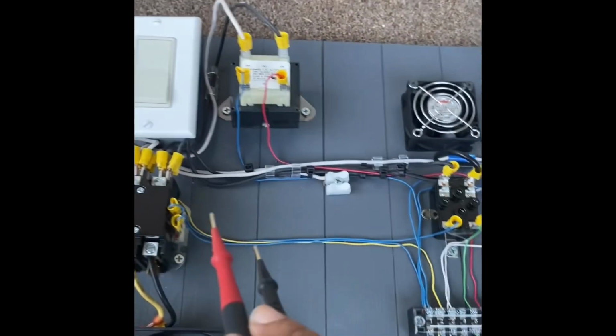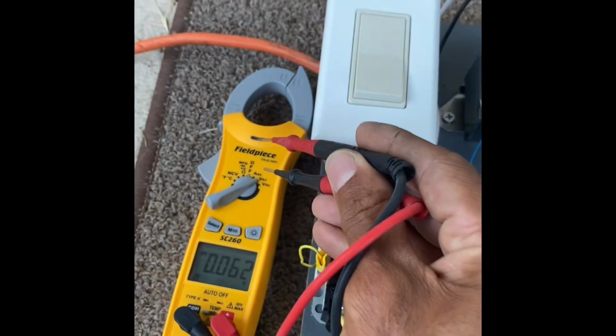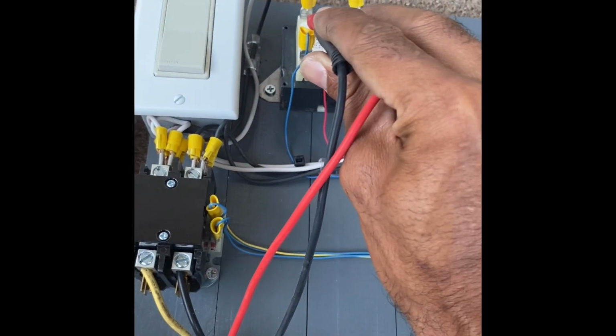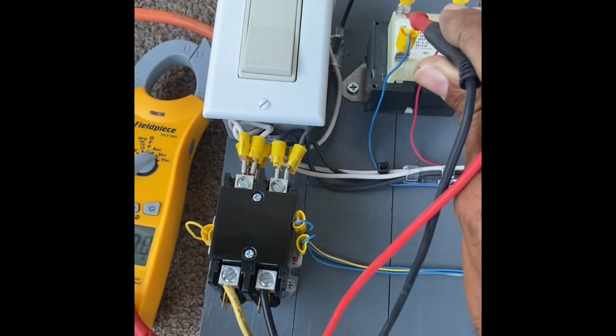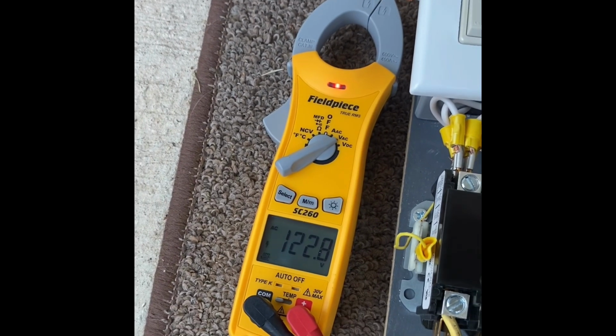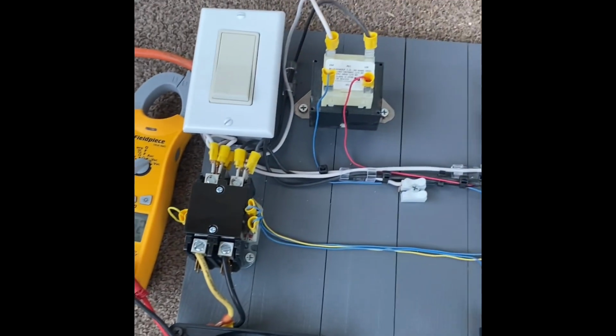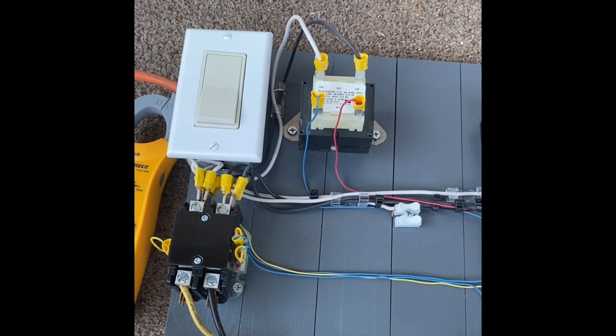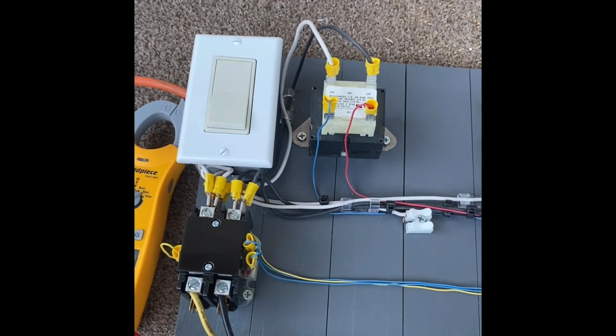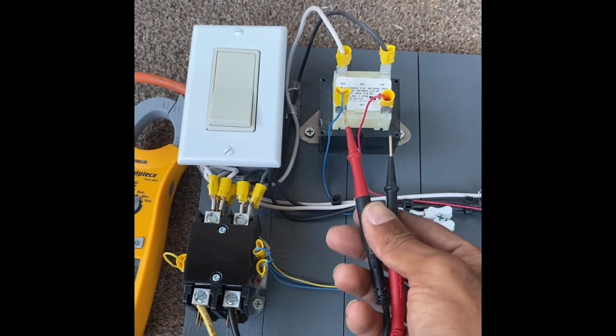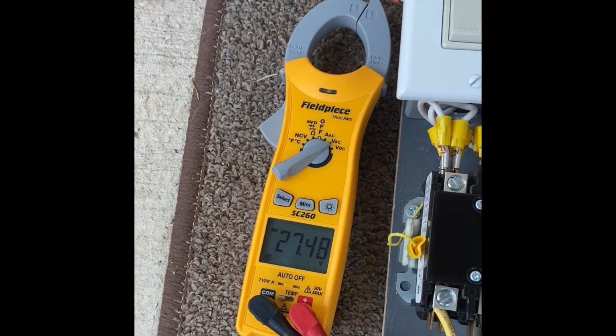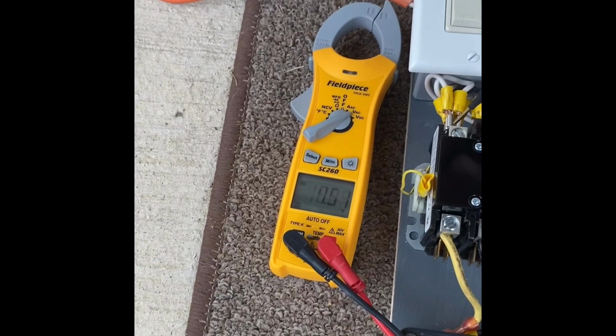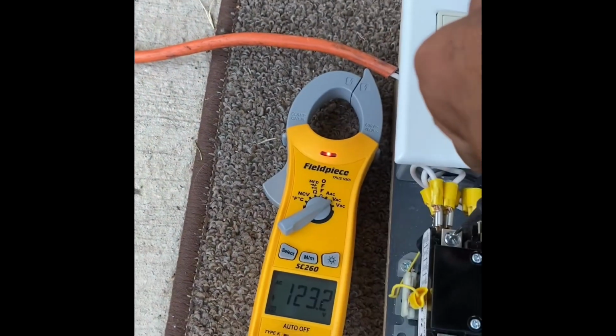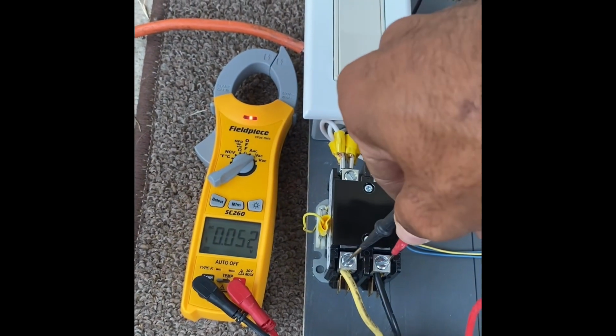So now we're gonna check power in voltage. Now we have 120 volts. Now we're gonna see if we are getting 24 volts on the other side of the transformer. I'm gonna put one lead over here and the other one over here. And yeah, we've got 27 volts. We've got voltage going into the contactor. Now we don't have anything coming out because it's not really calling for cooling.